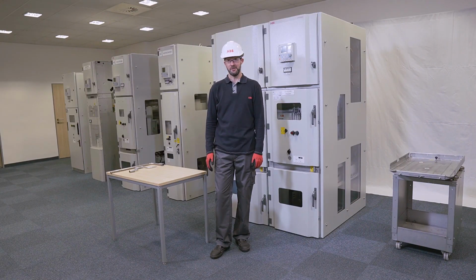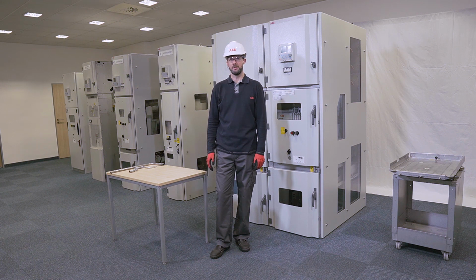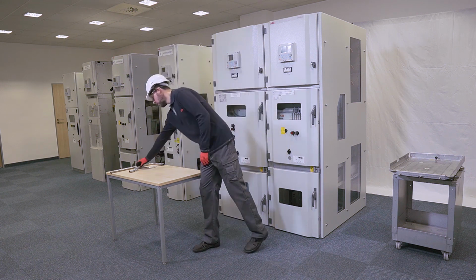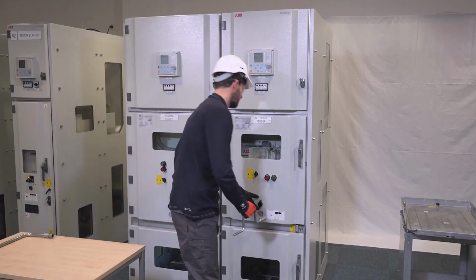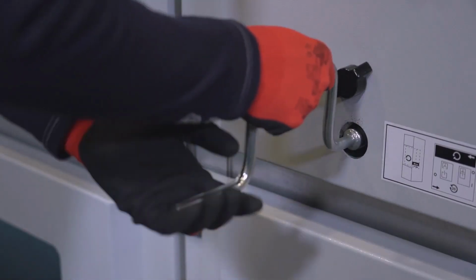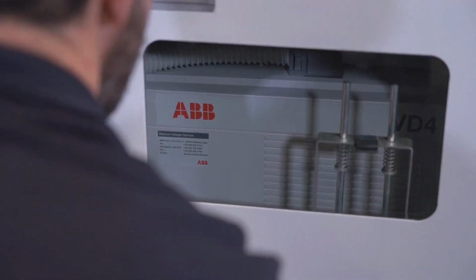The de-isolation is performed by racking the circuit breaker. Open the operating shaft, engage the lever with the shaft, and rotate clockwise to reach the final service position.